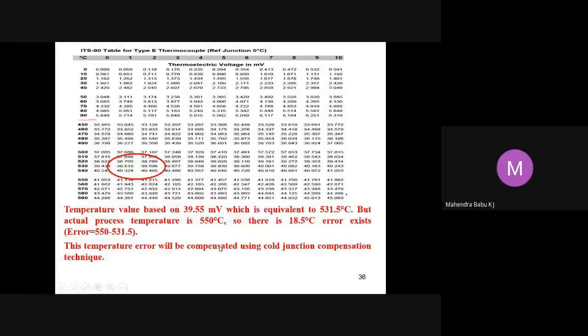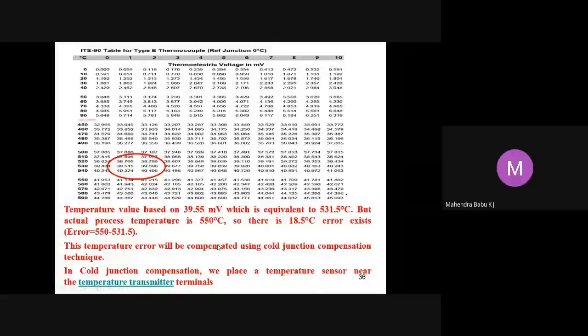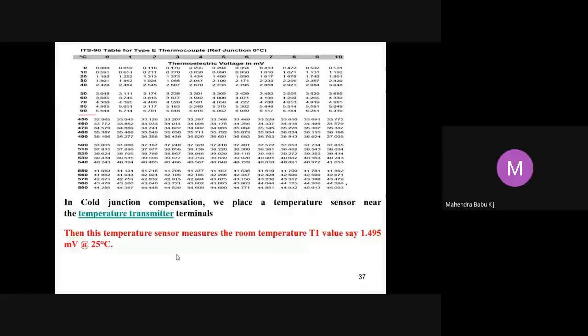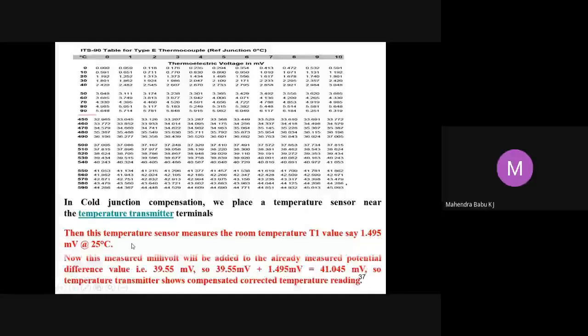As I said, in cold junction compensation, the temperature sensors are placed near the temperature transmitter terminals. Suppose you use cold junction compensation; let's check how the error is minimized. If the temperature sensor is placed near the temperature transmitter, the room temperature T1 is 25 degrees Celsius, and the value corresponding to that is 1.495 millivolts. The sensor will read 1.495 millivolts. Now this measured millivolt value is added to the already measured potential difference of 39.55 millivolts, which comes to around 41.045 millivolts.